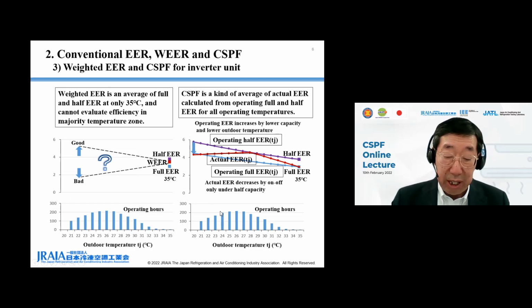This page shows weighted EER and CSPF for inverter or variable capacity unit. The left figures show tested full and half capacity EER at 35 degrees C and calculated weighted EER and operating hours at each outdoor temperature, which is same as the previous page. In this figure, WEER is a weighted average of full and half capacity EERs at 35 degrees C and cannot evaluate efficiencies at other lower temperatures in majority zones. The right figure shows calculated full and half EERs and actual EER and operating hours at each outdoor temperature.